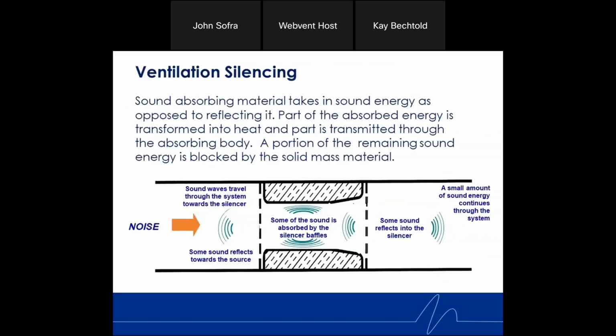Now, how do silencers work? Okay, you've got to let air pass through these. We call it a top and bottom where you see the hatch marks. Those are called baffles. The faces of the baffles are all perforated metal. The entrance noses of the baffles are solid metal. We stuff those baffles with insulating media, at all times plenum rated. Now we're looking at a plenum rating, even more stringent than a Class A rating.